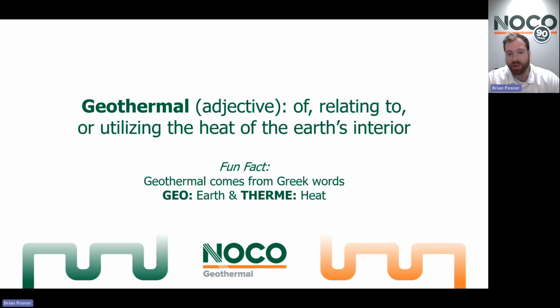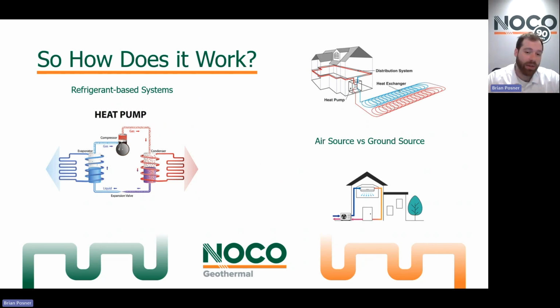So again, to make that distinction, geothermal energy production is going thousands of feet deep to create steam, turn turbines, and create energy. Geothermal heating and cooling, which is what NOCO is doing, is only going a few feet to a few hundred feet deep to get those near constant temperatures of the Earth's crust to be a heat sink for our heating and cooling systems. So again, geothermal is not making energy like a solar system is doing. It's utilizing energy. And it does so in a more efficient manner than most heating and cooling systems. And we'll get into that math a little bit later on.